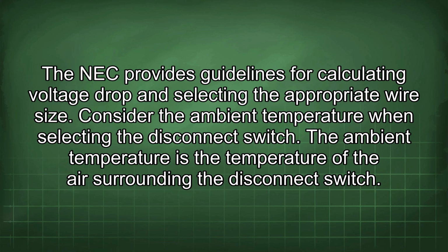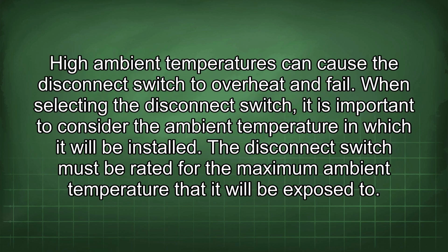Consider the ambient temperature when selecting the disconnect switch. The ambient temperature is the temperature of the air surrounding the disconnect switch. High ambient temperatures can cause the disconnect switch to overheat and fail. When selecting the disconnect switch, it is important to consider the ambient temperature in which it will be installed.